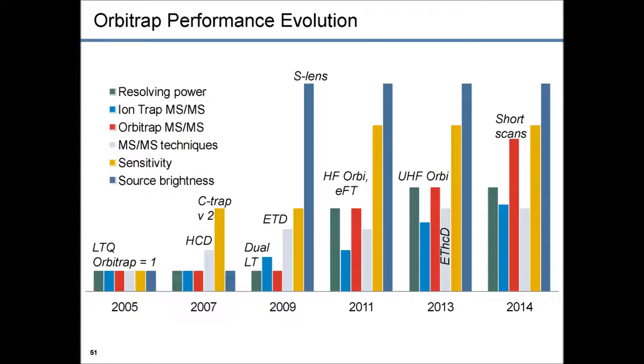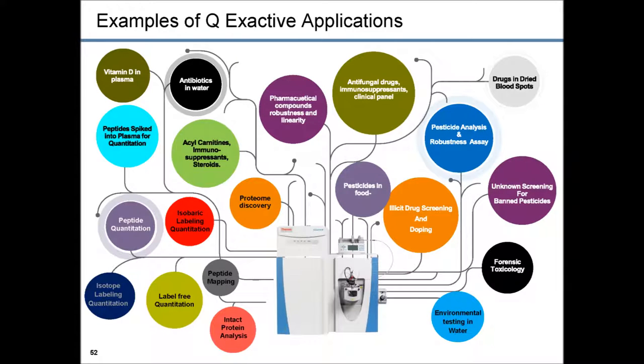This is how Orbitrap technology has progressed over the last 10 years. Starting from the performance of the LTQ Orbitrap, following different analytical parameters: the brightness of the source increased by an extraordinary amount, sensitivity of Orbitrap detection by a factor of 7, speed of Orbitrap MSMS by a factor of 8, and resolving power in one second by a factor of 5 — sort of trying to defeat Moore's law. These are just different applications of this tandem instrument.